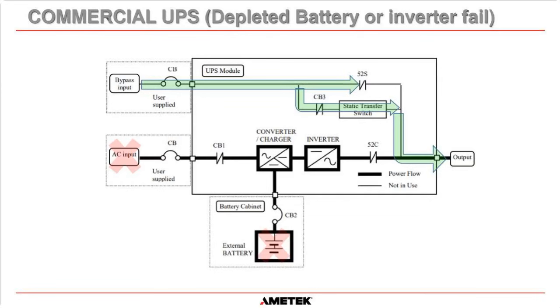And then the last thing that the commercial UPS does in that circumstance is once the initial transfer has taken place using the static transfer switch, it will then close this contactor here, and it will bypass the SCRs in the static switch, and the bypass will feed all the way through this line here. So the static switch in a commercial UPS is usually only rated for a very short period of time to allow the initial transfer to take place, and then this contactor here takes over. Okay.